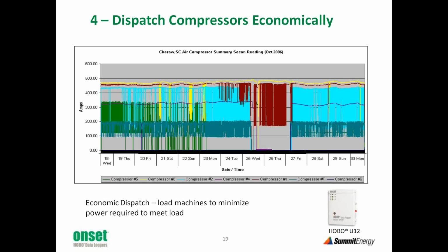Each color is a different compressor. There are a lot of things to learn from these diagrams, but the most important I'd like to point out is that several are modulating, trying to control pressure. They're working against each other. What you would expect to see here is all the machines that are running run at a base load at their most efficient point, and then one compressor that's good at partial load modulates in order to maintain the pressure in the system. So in this particular case, we can see the controls are not working properly, and we have more than one machine loading and unloading.